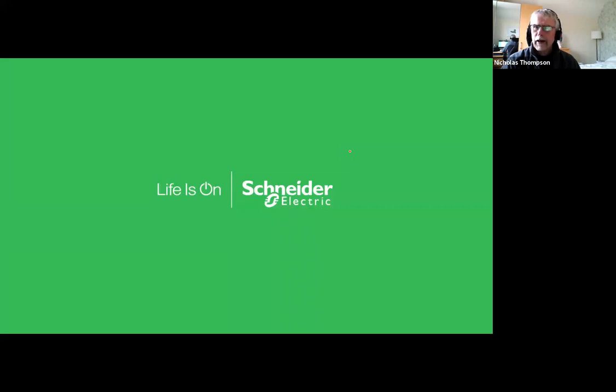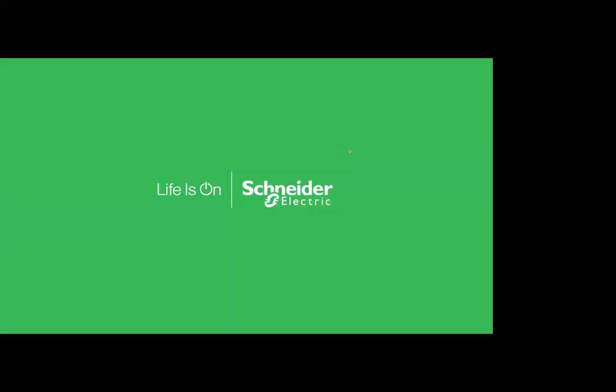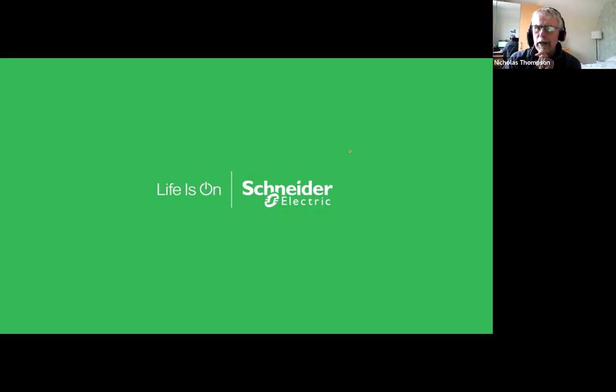So Mohammed asks how on earth earth current sensing works in the time limit fuse, I think it was on slide page 16. It probably was. Grids are now introducing power electronics, VFDs, which introduce harmonics. The way that a very simple time limit fuse works, you're working on instantaneous at either 25 amps or 30 amps if you haven't got a fuse. So with a time limit fuse, it's not going to detect what harmonics you've got in there, if that's a way of describing it.